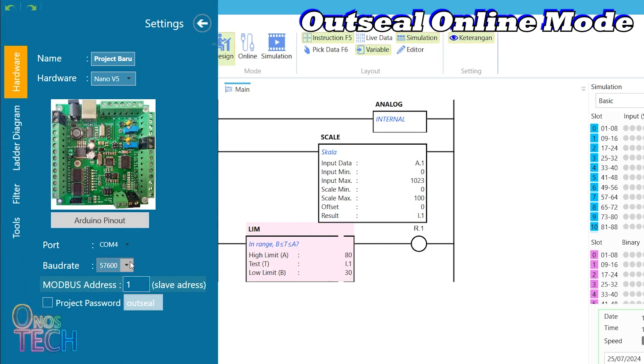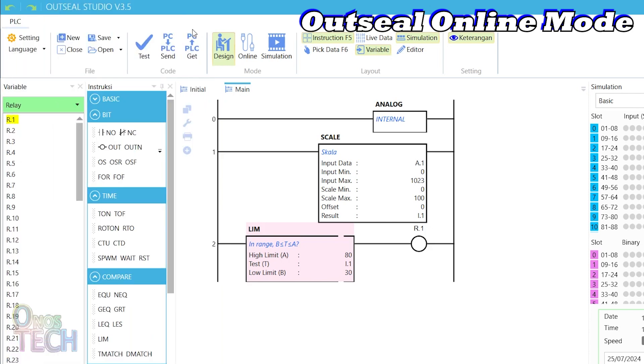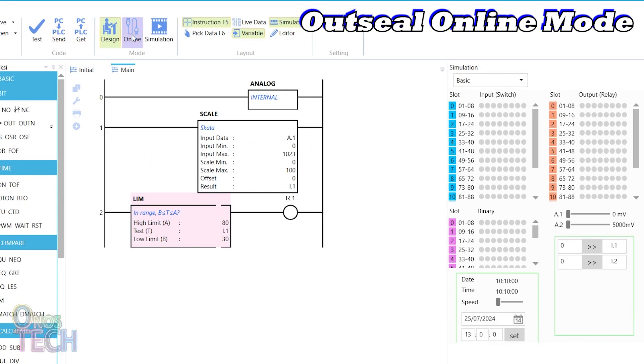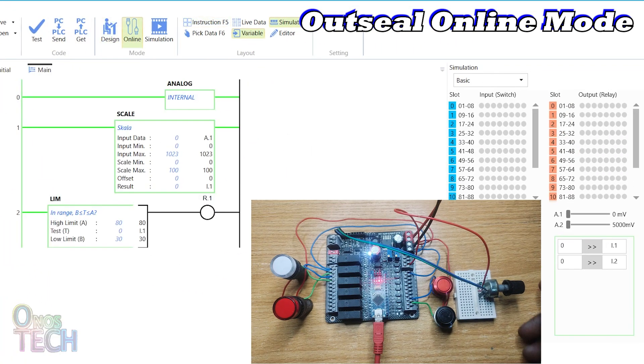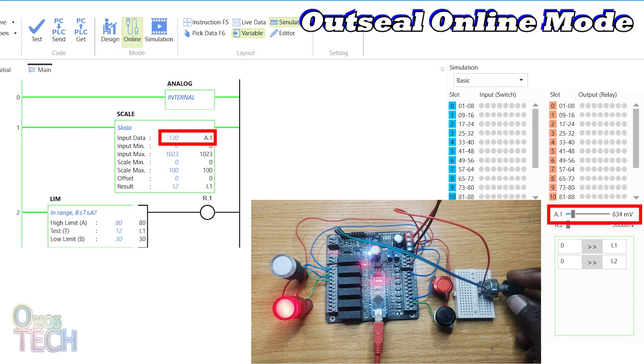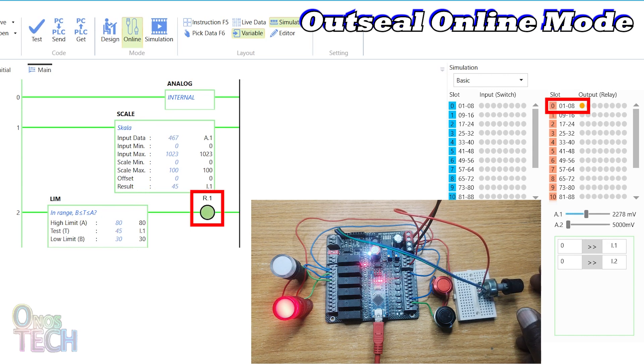Ensure that the PLC baud rate setting is 57600 or 115200 before entering online mode. As the potentiometer is adjusted, a live I.1 value can be seen on the instruction and the simulation window. R.1 lights up on the instruction and the simulation window when the I.1 value is between 30 and 80.